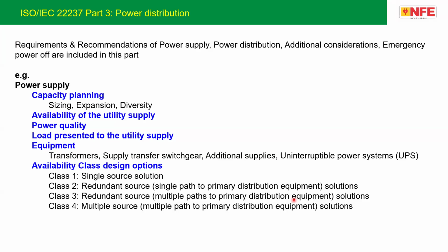So we are going to discuss the power supply. The power supply is the main power we are getting from the supply authority for the facility or data center. It should be designed so that we can meet the availability class of the data center. The main part of the power supply is capacity planning, and sizing plays the key role. The maximum capacity of the power supply to the data center shall be sized to accommodate the maximum planned IT load and the future growth and technology development, including the increased power density of the IT equipment upcoming in the future.